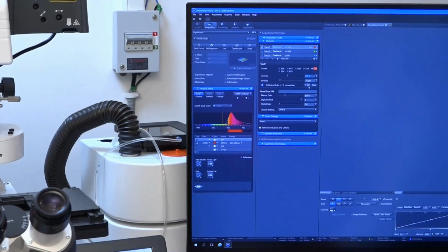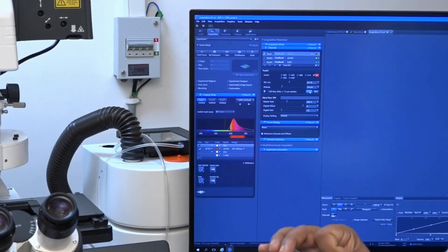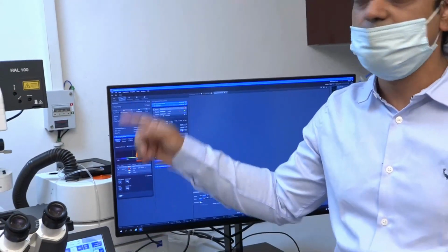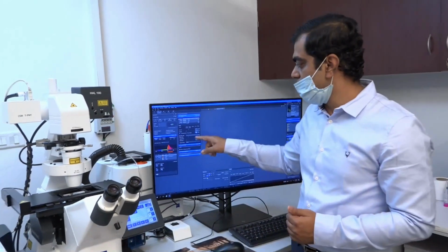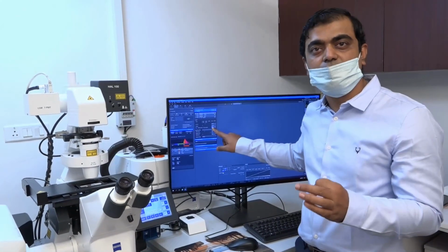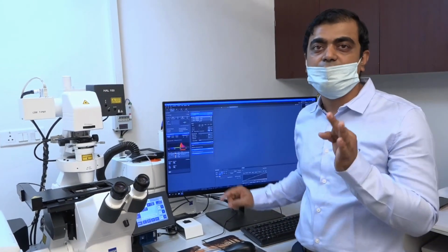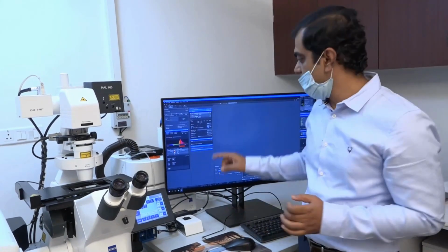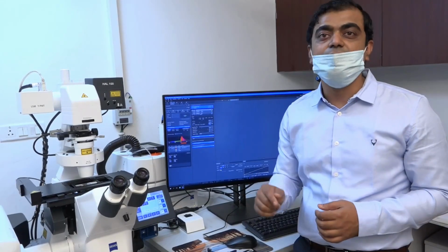Now as this is a confocal system, the instrument has to be optimized based on the pinhole aperture which is internally present at the conjugate focal plane of this microscope. Now at the conjugate focal plane, the pinhole aperture size or diameter entirely depends on the point spread function, which we say here as 1 Airy unit.